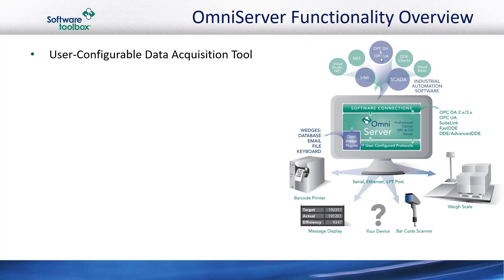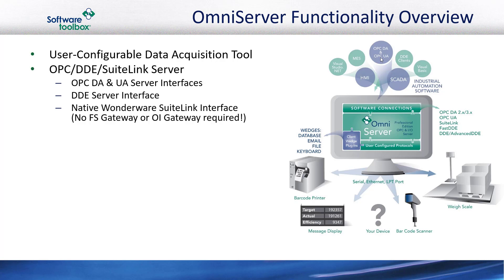OmniServer is a user-configurable data acquisition server that uses a pattern matching engine, allowing you to configure a pattern of bytes for a specific device referred to as a protocol. For making data available to HMIs, SCADA, and other visualization or client software such as AVEVA Wonderware solutions, OmniServer supports OPC DA, OPC UA, DDE, and has a native Wonderware SuiteLink interface, not requiring FSGateway or OIGateway to get connected.